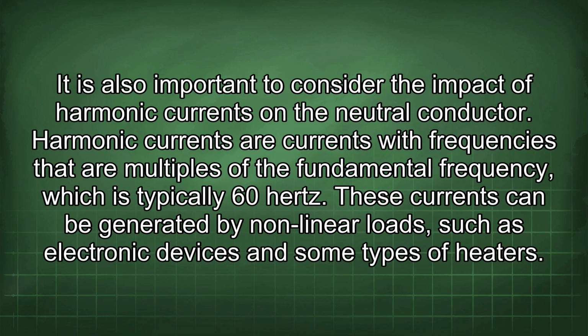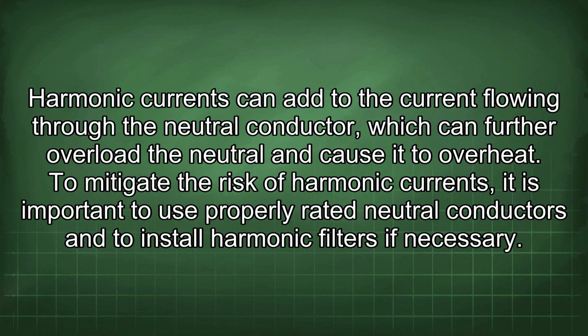It is also important to consider the impact of harmonic currents on the neutral conductor. Harmonic currents are currents with frequencies that are multiples of the fundamental frequency, which is typically 60 Hz. These currents can be generated by nonlinear loads, such as electronic devices and some types of heaters. Harmonic currents can add to the current flowing through the neutral conductor, which can further overload the neutral and cause it to overheat. To mitigate the risk of harmonic currents, it is important to use properly rated neutral conductors and to install harmonic filters if necessary.